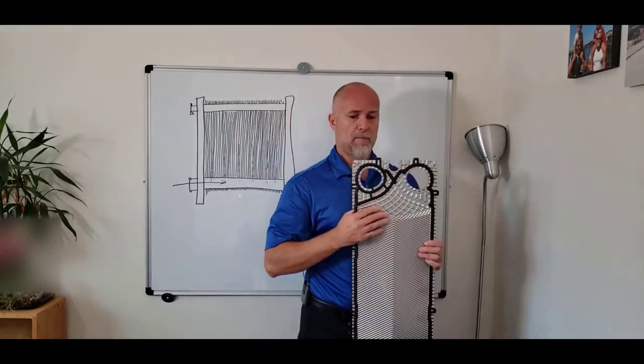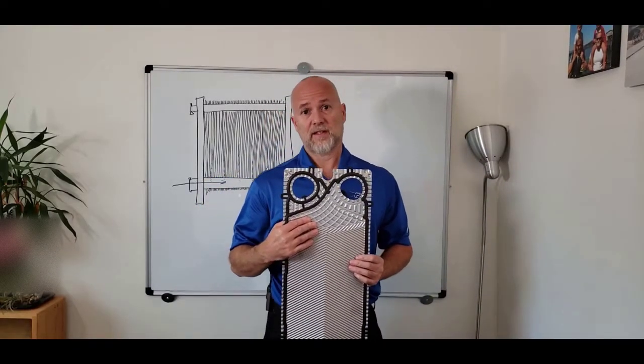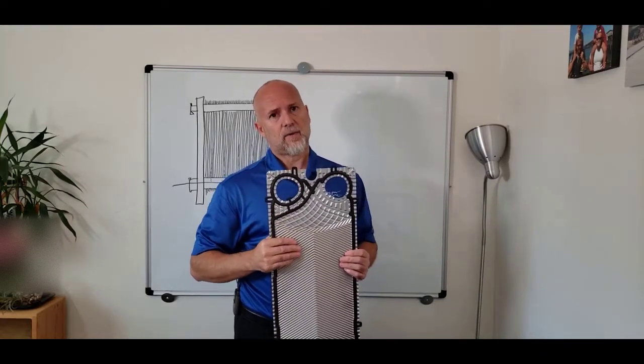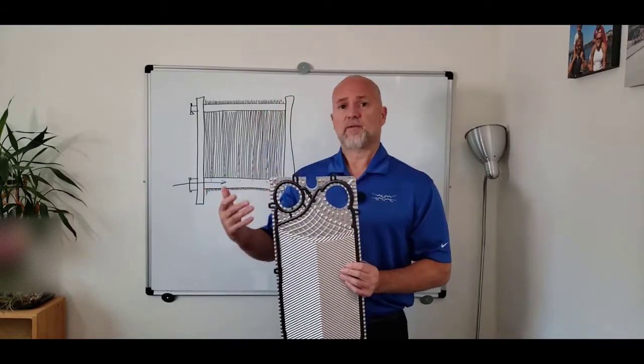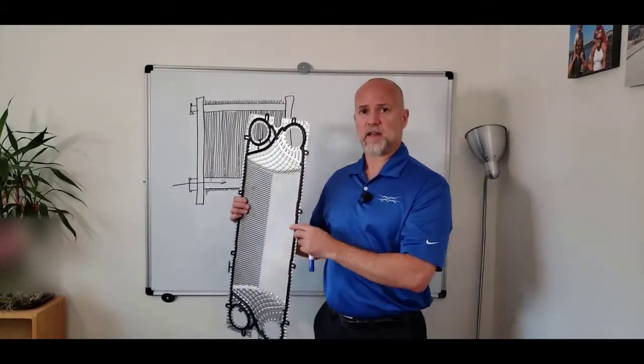It has been proven that the increase in efficiency is actually significant, up to 25-30%, which is amazing if you think about that. And that is another reason why we say that the heat transfer area, so the amount of plates that you have in a heat exchanger, is not necessarily a good indicator anymore.